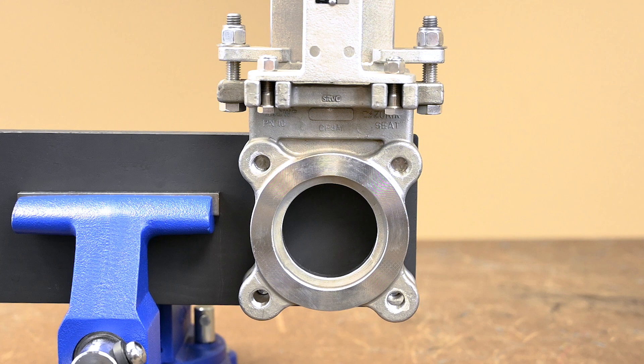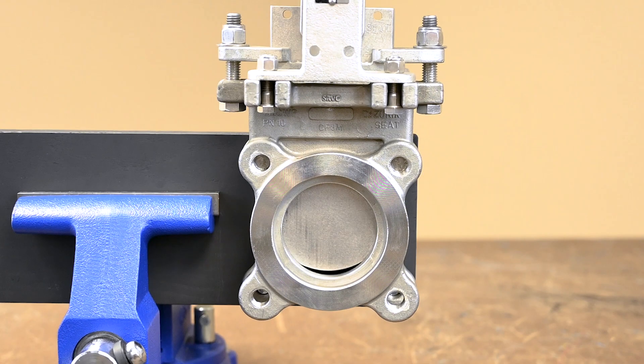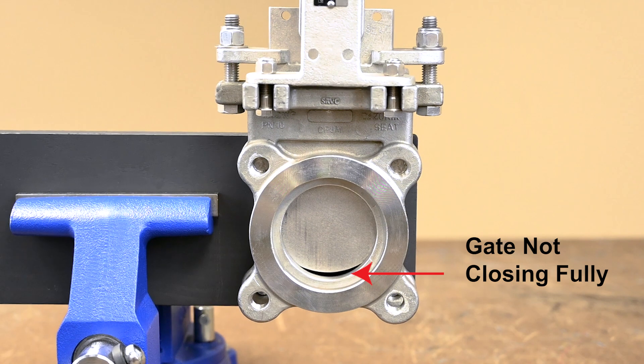To adjust the cylinder stroke, it's recommended that the valve be removed from service. Step 1: Set the valve closure distance. The actuator should close the gate fully against the jambs. Check this by closing the gate.